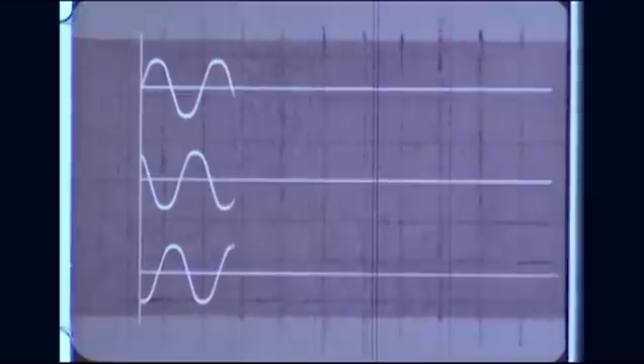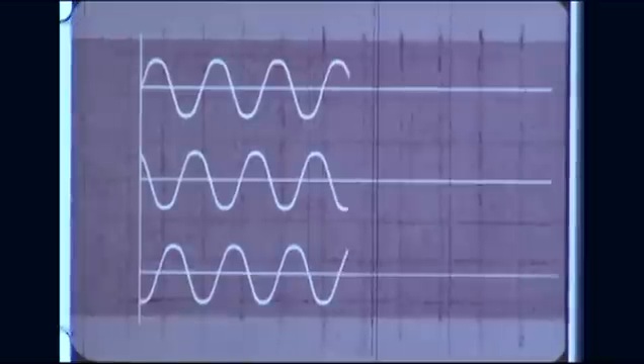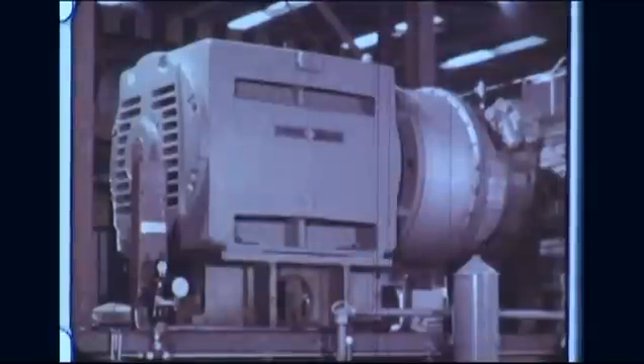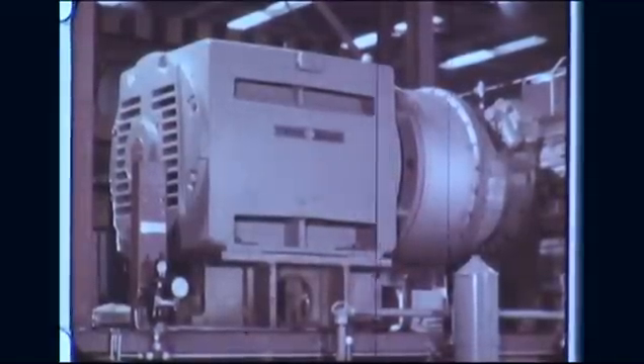Thus far we have been discussing single-phase current, generated by one rotating coil. In practice, however, three-phase voltage is generated in electric power systems. In a three-phase generator, three coils are placed 120 electrical degrees apart, so the three voltages generated are 120 electrical degrees apart, meaning three different currents are generated, each displaced from the others by 120 electrical degrees. Three-phase generators are popular because they make more efficient use of the generator's iron core and copper windings than single-phase generators. Three-phase current can be distributed more efficiently, and large three-phase motors run better and are less expensive than single-phase motors.